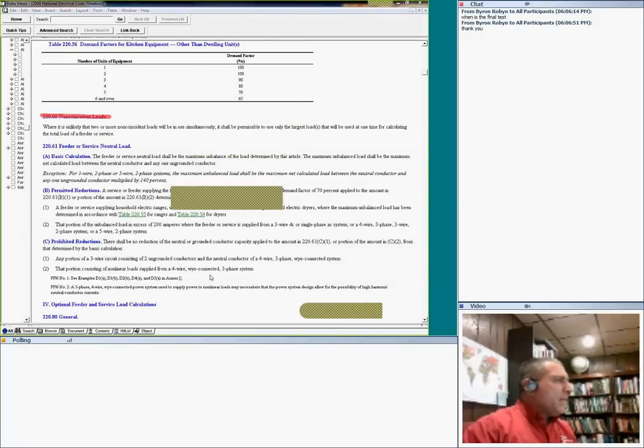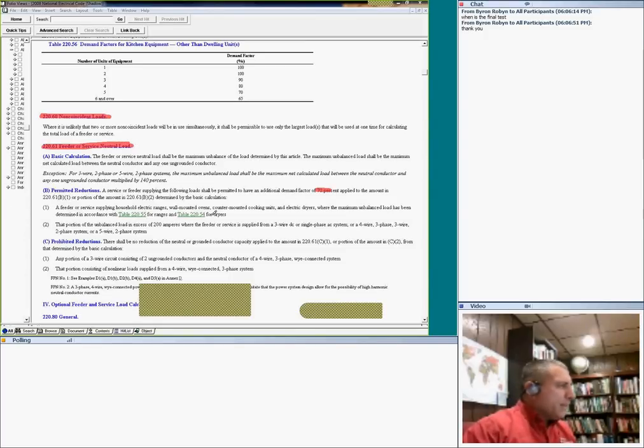Noncoincident loads, guys. If you have heating and cooling systems, you choose the largest of the heating and the cooling system. And one more, guys, the neutral. For your neutral, you can get 70%, for anything in excess of 200 amps, they derate it by 70%. For ovens and ranges, wall-mounted ovens and so on, you can cut them by 70%. So these allow you to have a smaller feeder for the neutral. But no derating if you have harmonics.